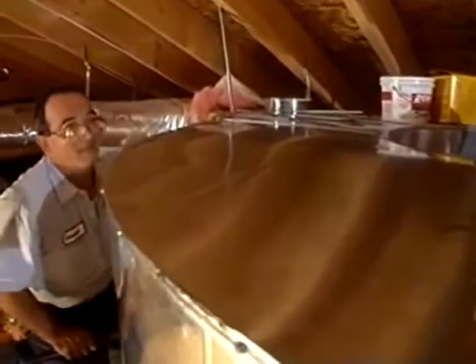Leaky ductwork is certainly among the top reasons for energy loss and comfort complaints in a home. But there are also other reasons. Ductwork that has been constricted, the air pathway, can also cause comfort problems. When we think about airflow, we should think about water coming out of the hose. And you want to be able to get the maximum pressure out the other end. And the more bends and kinks you put in that hose, the slower the water is going to come out. Whereas if you make that hose nice and straight, the water is going to flow continuously. We're going to have the maximum amount of pressure coming out, and that's really what we're looking for.